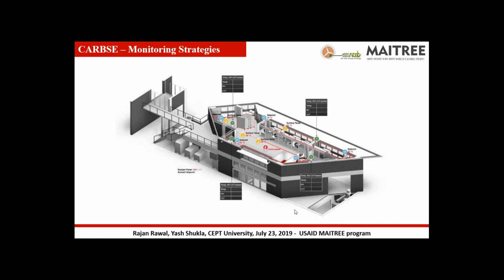So for example, if we have a lesser number of occupants present in the building, we would turn off the ventilation fans so that our energy consumption reduces and our outdoor air quantity reduces, but our CO2 level stays within a limit below 1000 parts per million. And when our carbon dioxide level goes above 1000 parts per million, then we start additional ventilation fans to ensure that the indoor air quality and health of our occupants do not get affected. But at the same time, it increases the energy consumption of the building.